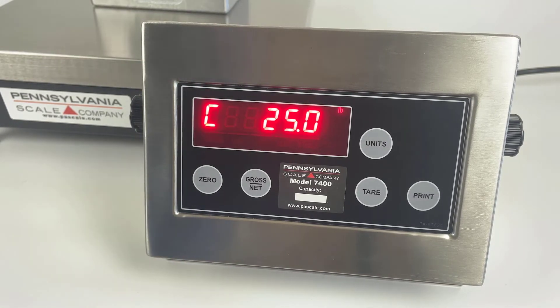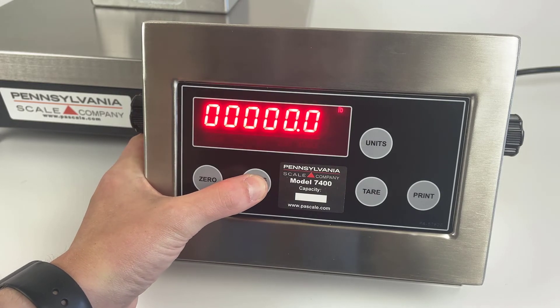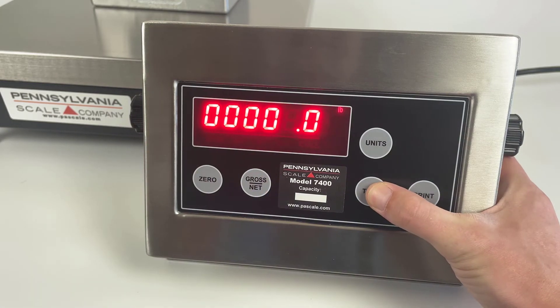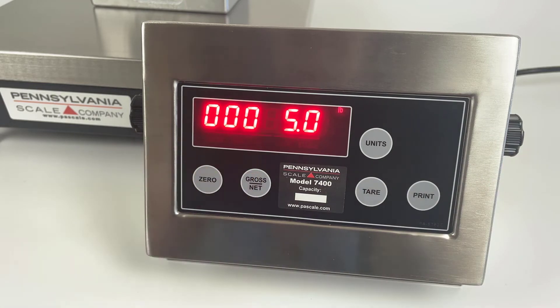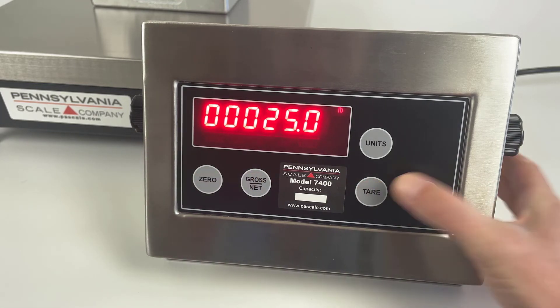Next, place your weight on the scale. It shows you a live reading. If it's incorrect, use the gross net key to select the tens place and the tare key to increase the value. The print key then confirms, and the dashes show that it's calibrating.